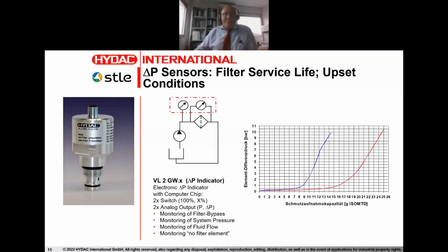Very interesting. Now, switching over to instrument monitoring, this is a differential pressure sensor, and we can monitor the differential pressure across the filter element, which tells us a couple of different things. First of all, if we look at the red curve versus the blue curve, one of the things that we can say is that, ignoring what the dirt holding capacity on the bottom says, let's just assume that it's dirt added. This basically says that a lot more dirt has been circulating in the system, because this should be time, actually, that would be more representative if we're talking about a normal operating system. So it requires less time, say 14 minutes, to plug the filter as opposed to 25 minutes, because there's twice as much dirt floating within the system.